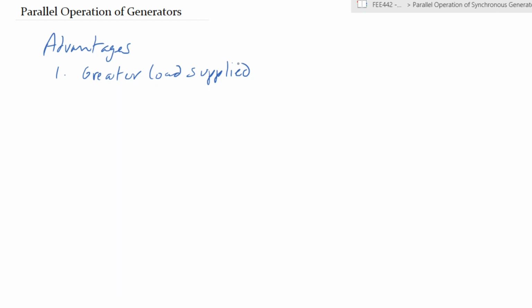Right, so when we have a set of generators, there are certain advantages to operating them in parallel. Operating them in parallel would mean that you have more than one generator in the same area, two or more, that you would be able to link together and be connected to the same set of loads. So the advantages of this type of setup would be, first of all, a greater load can be supplied. Obviously, if you have a 10 MVA load, you can supply it with a series of 1 MVA generators.